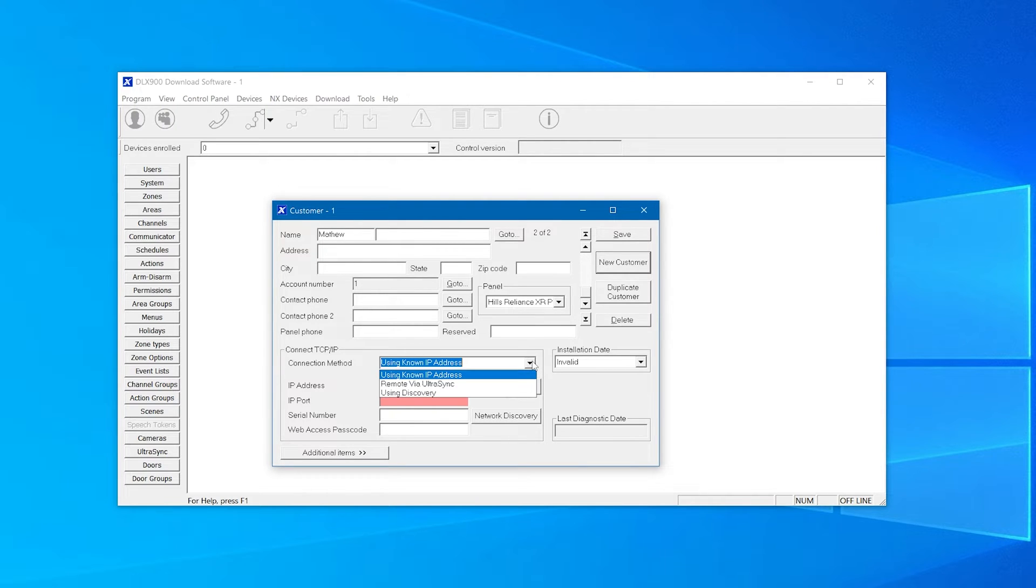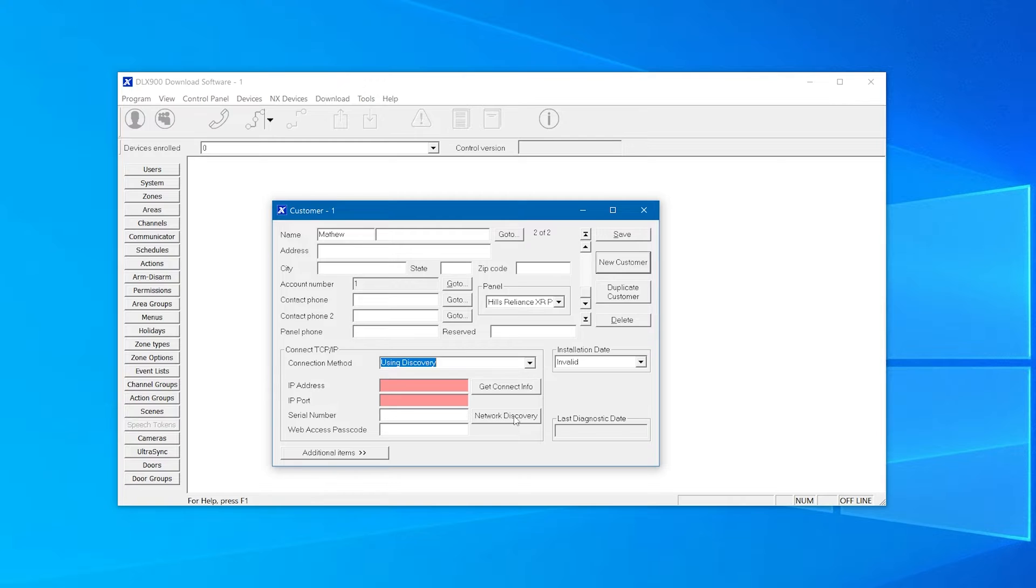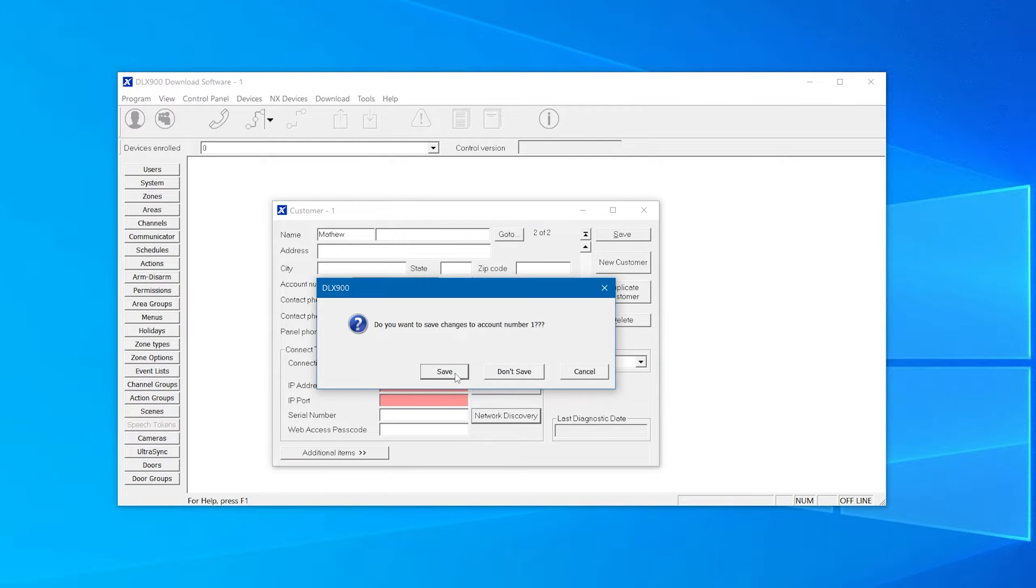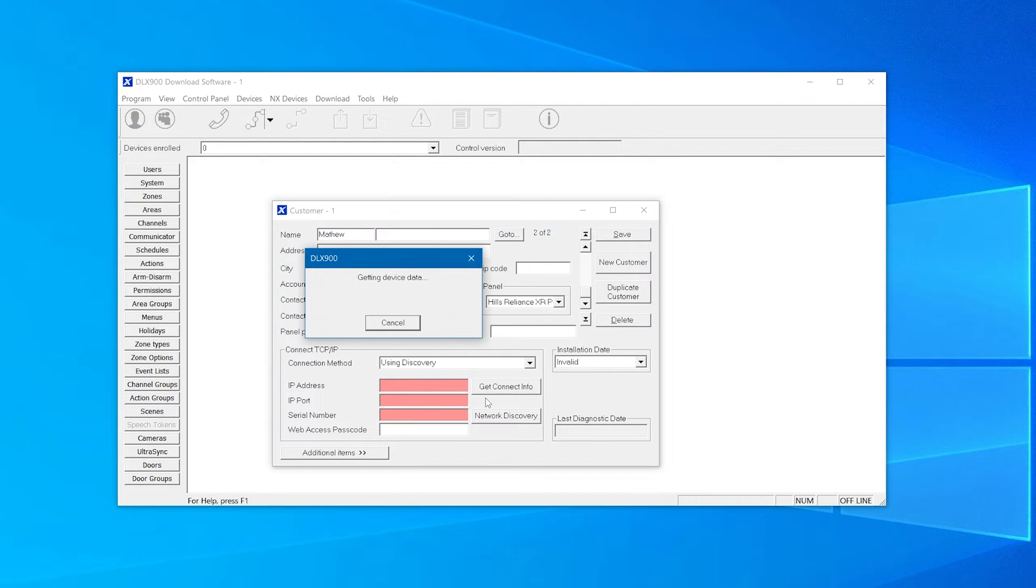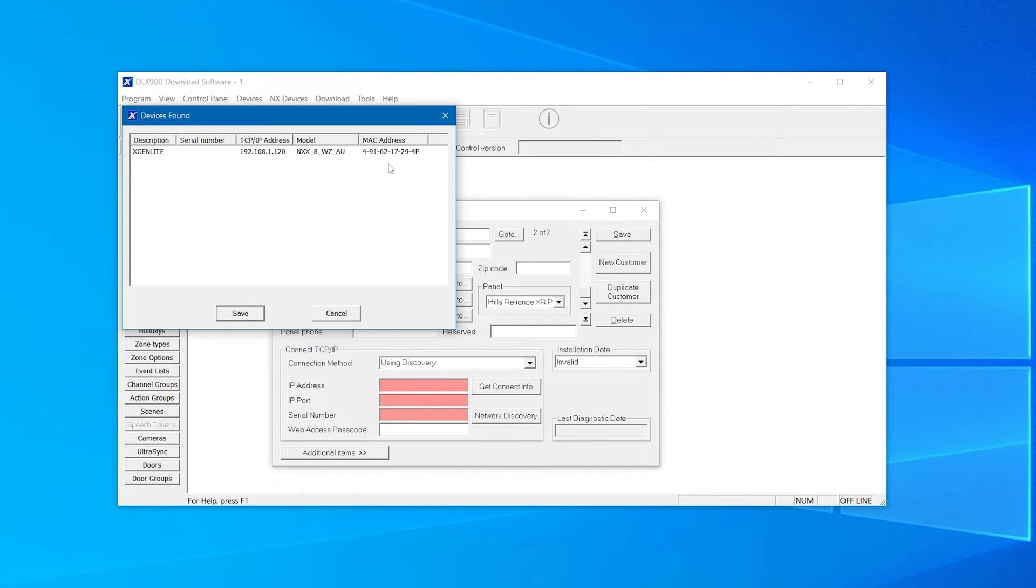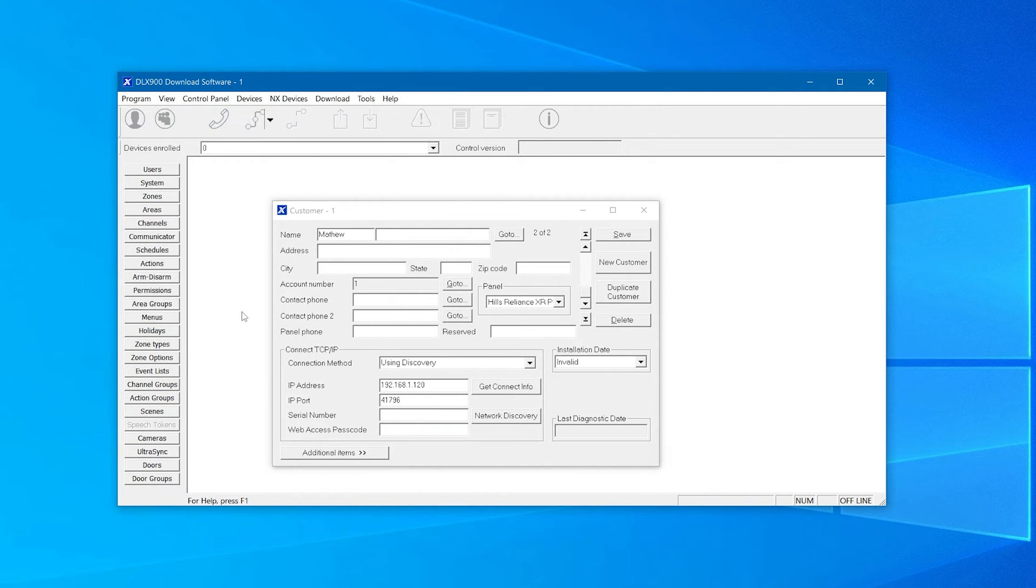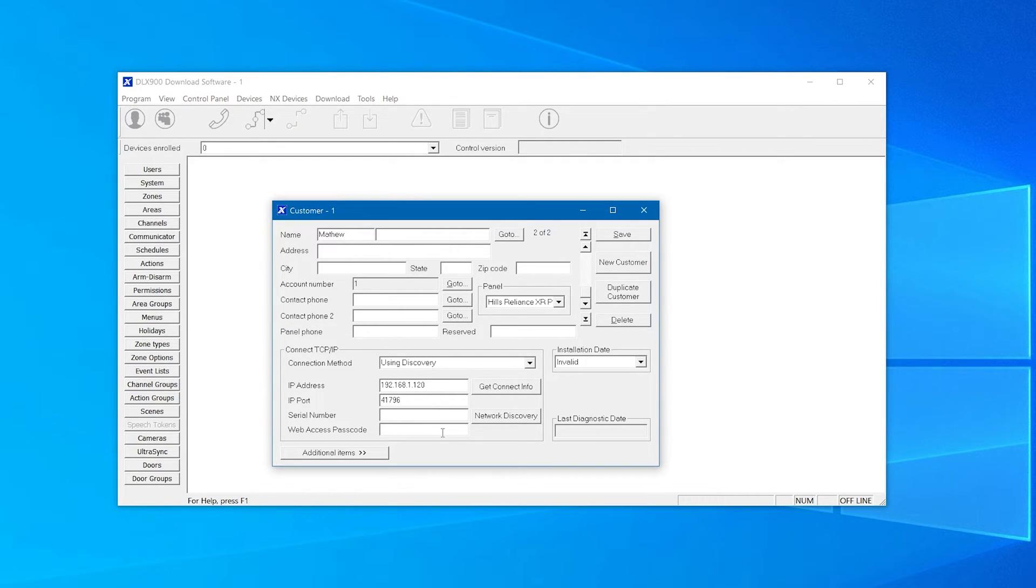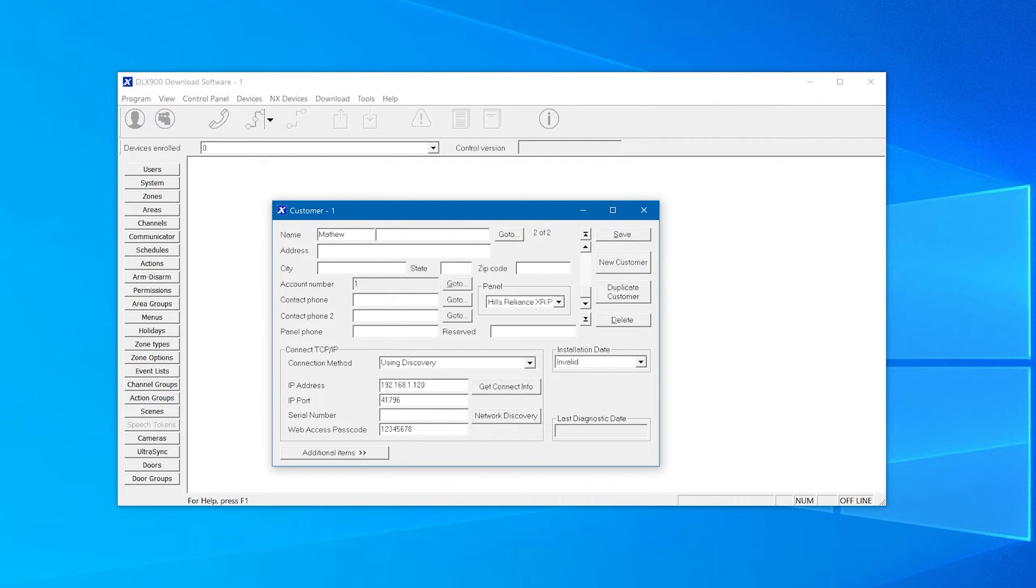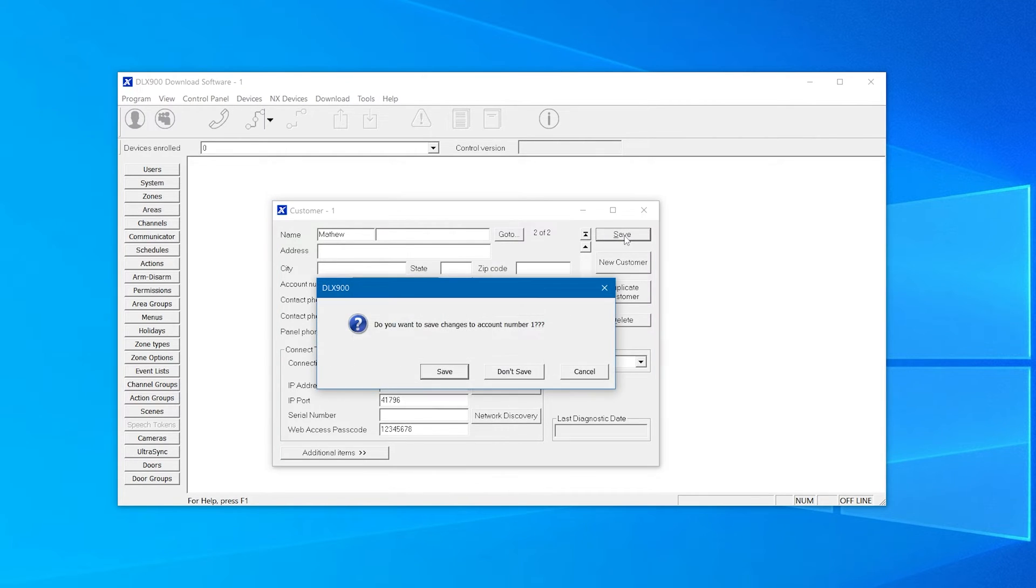In this example we'll select the discovery method. The discovery method scans for panels on the same LAN network. Select the panel after it has been found and click save. Information from the panel including the IP address, port number, and serial number will be relayed into the appropriate text sections. The web access passcode for the panel must be entered in order to be able to connect.